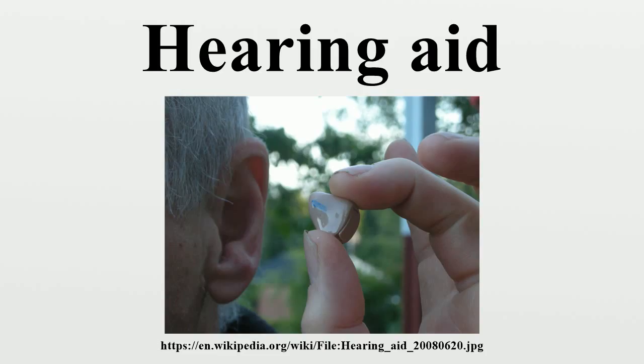The compression effect. The amplification needed to make quiet sounds audible, if applied to loud sounds, would damage the inner ear. Louder sounds are therefore reduced, giving a smaller audible volume range and hence inherent distortion. Hearing protection is also provided by an overall cap to the sound pressure. Also a protective value is impulse noise suppression, available in some high-end aids. The initial fitting appointment is rarely sufficient, and multiple follow-up visits are often necessary. Most audiologists or hearing instrument specialists will recommend an up-to-date audiogram at the time of purchase and at subsequent fittings.